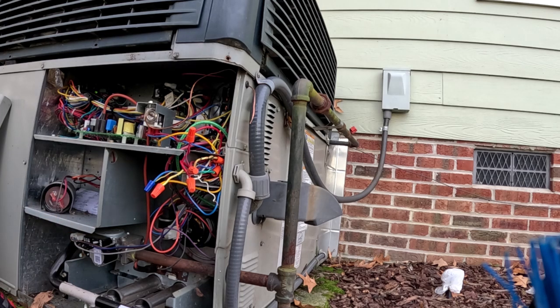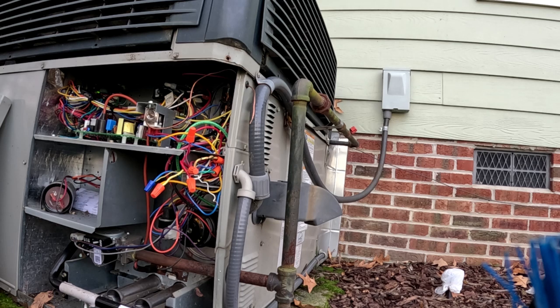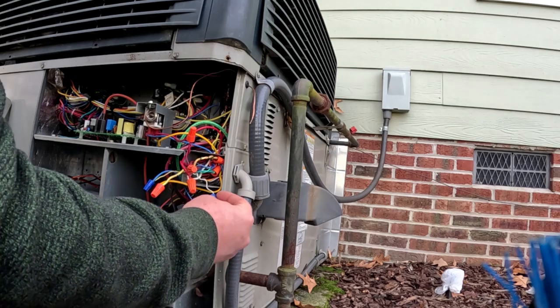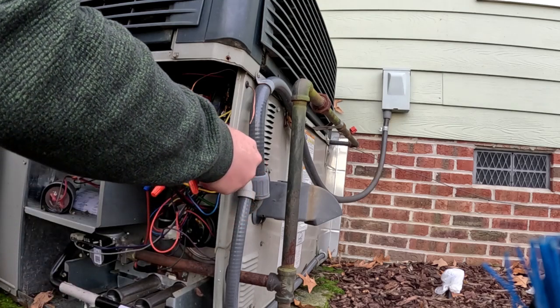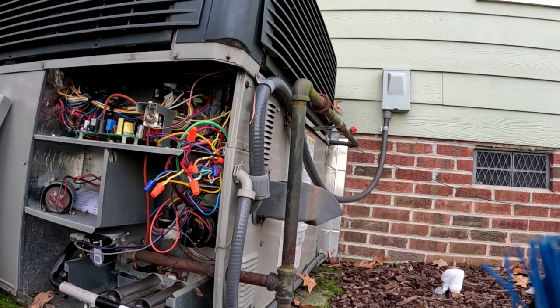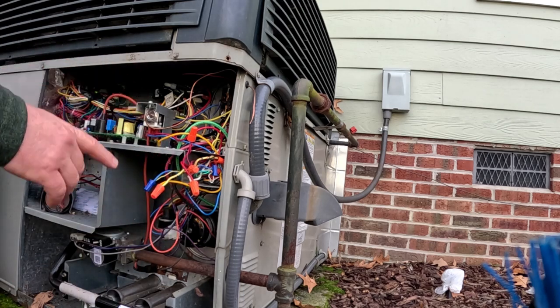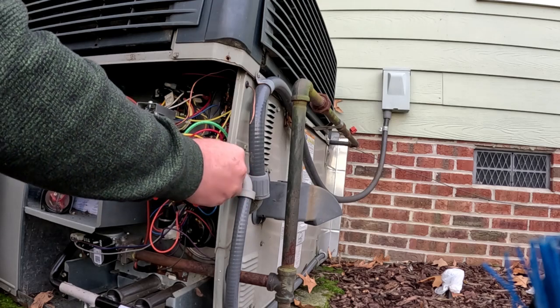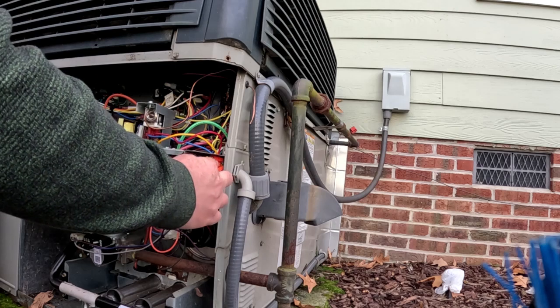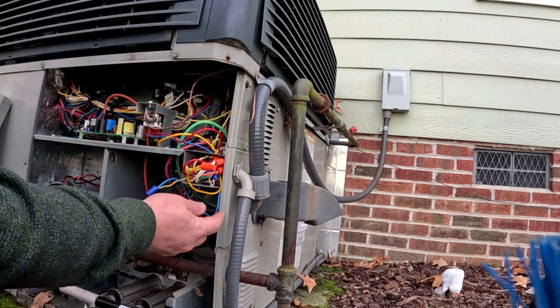I'm going to put a wire nut on that. This W wire that we were using for your furnace is not used anymore, and I'm going to disconnect it from the thermostat — it was connected to the terminal in there that was going to be used for the auxiliary purpose. It just blows my mind that the control board wouldn't be set up to know that if it gets a call for the furnace it doesn't need to run together with the compressor — just shut that down on its own. The newer ones don't do it either; the one I worked on yesterday didn't. So I'm going to go back in and turn the auxiliary function off on the thermostat.